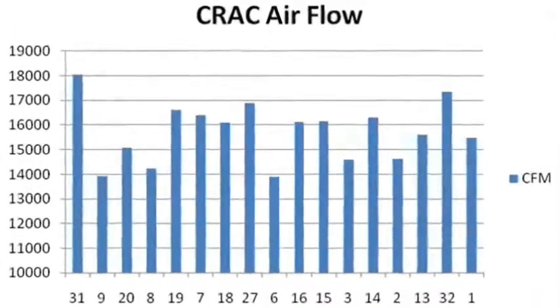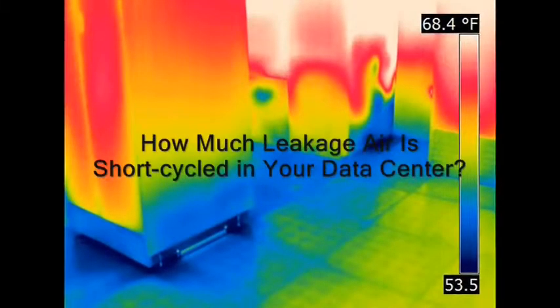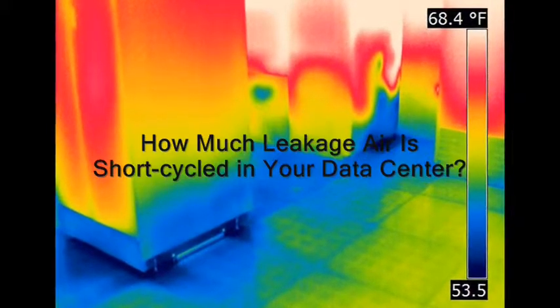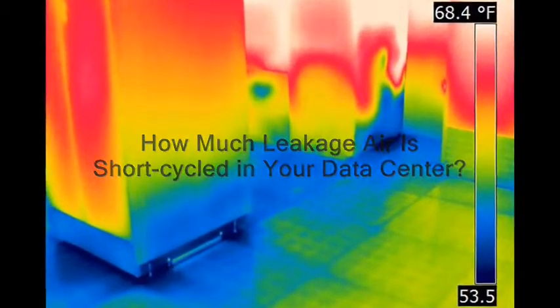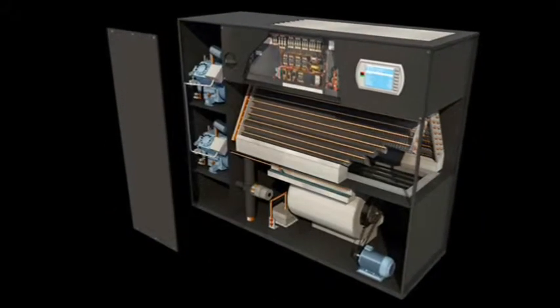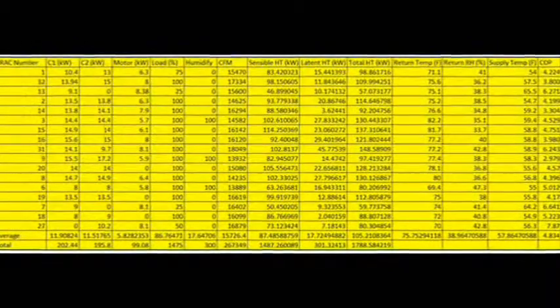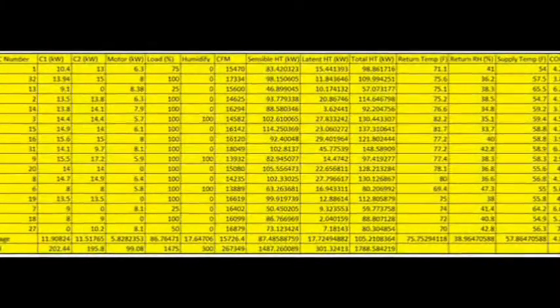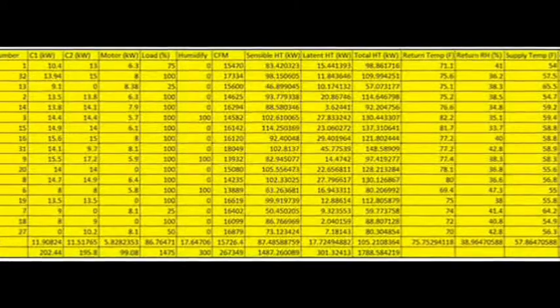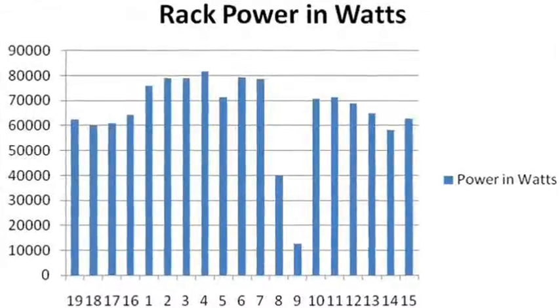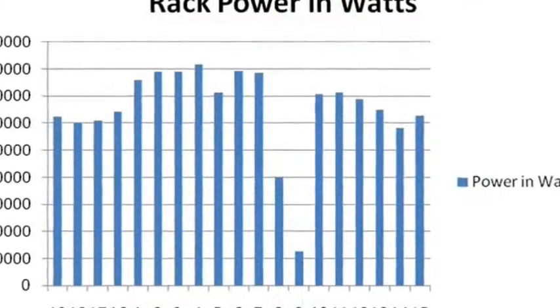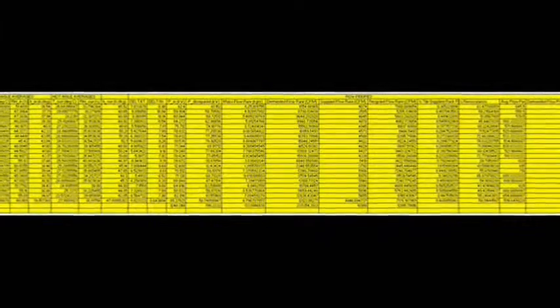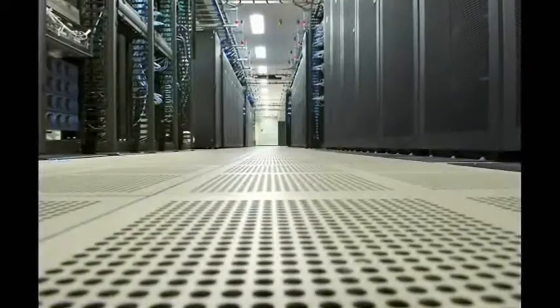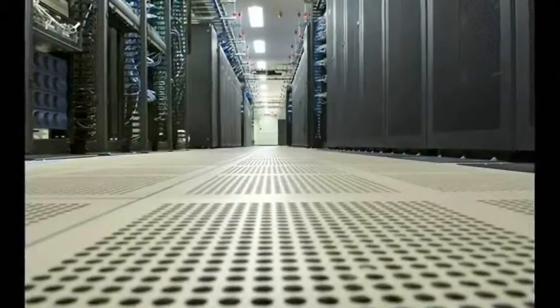We also measure flow rates through the CRAC units. We determine your leakage rate and show you how much CRAC unit air is short-cycled and essentially wasted. We conduct a CRAC unit performance evaluation highlighting power consumption, heat transfer data, coefficient of performance, and more to help identify units that are not operating to their potential. We provide extensive analysis of server power consumption and heat dissipation. We use this information to assess how well the localized and global cooling capacity and airflow meet the needs of your IT loads.